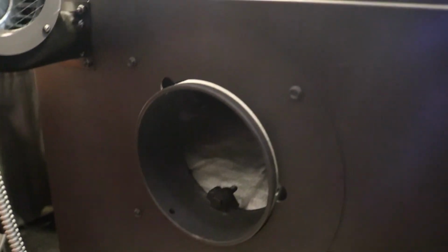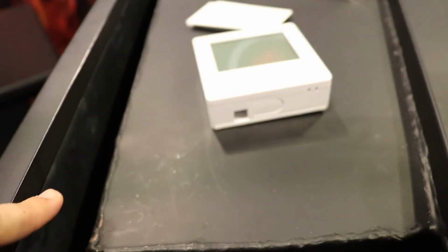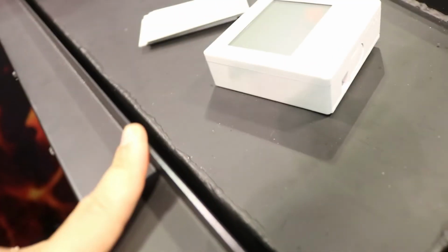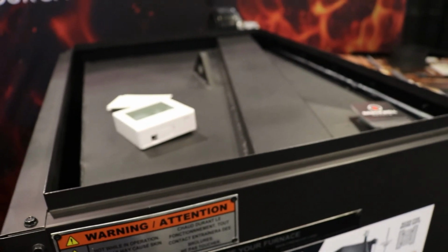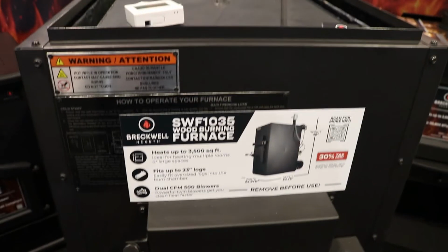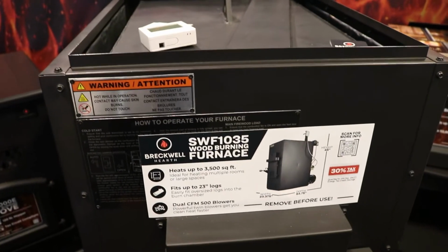This is going to be your flue location. As per standard most furnaces, it's going to be a rear vent, so you come out the rear with a T to take you up vertical. Something else I want to show you guys on the furnace is these air gaps. This is nice because this is also what creates a natural convection heat that's simply going to rise out of here even without a blower, because that's what this inner stove body and the outer sheet metal creates. It creates a nice convection, and then your plenum is going to attach here to the top of the furnace. So this is going to be how it comes, just like this, and then your installer will shape the plenum to connect it directly into your ductwork.